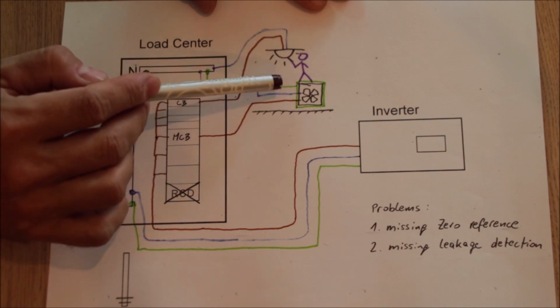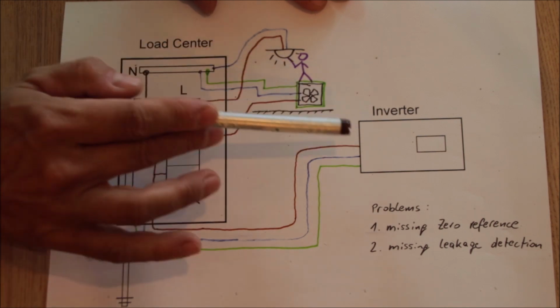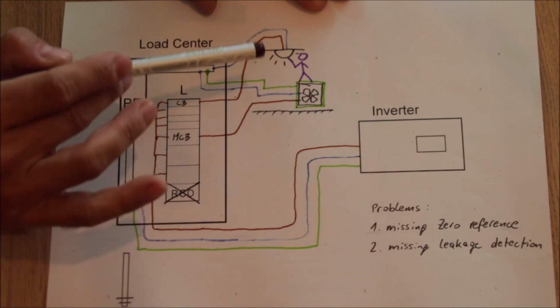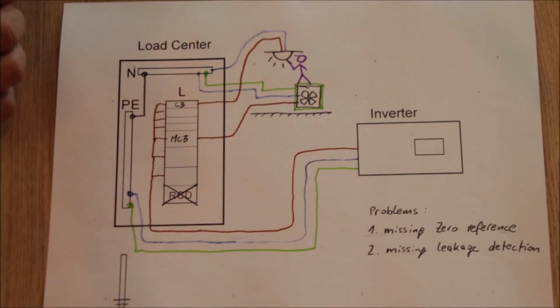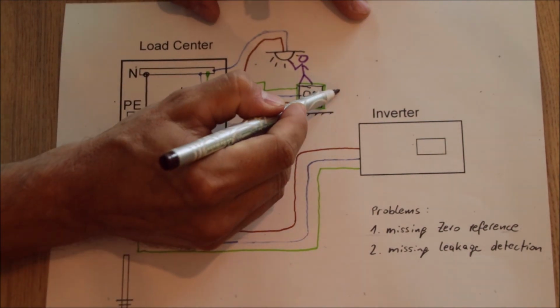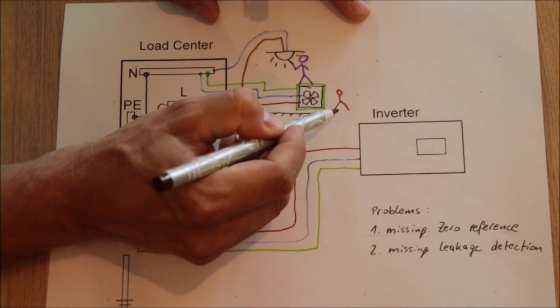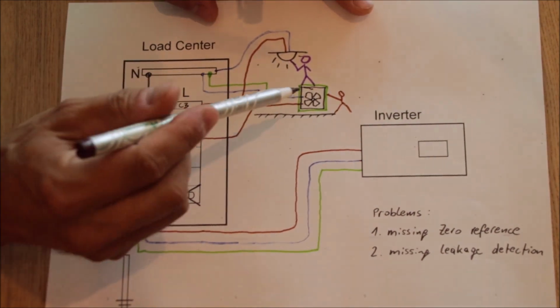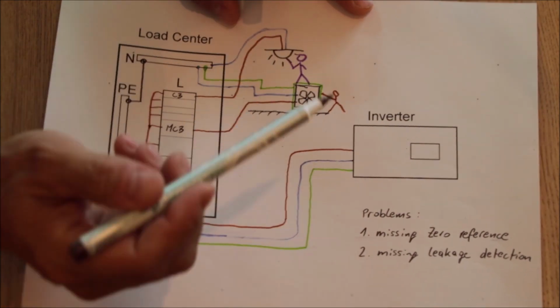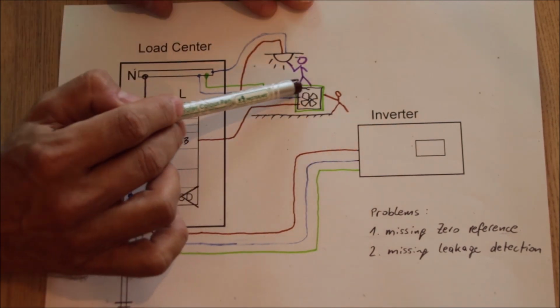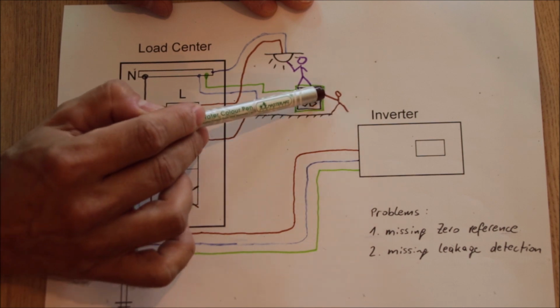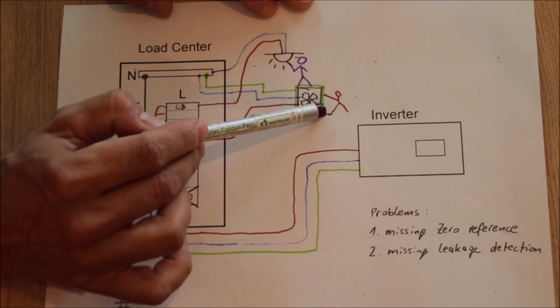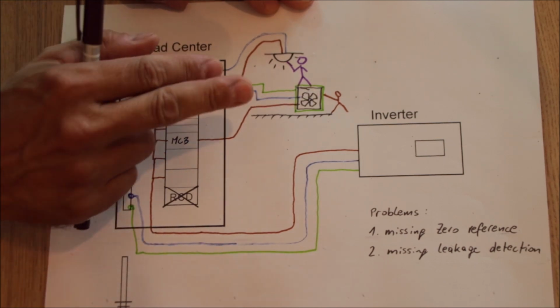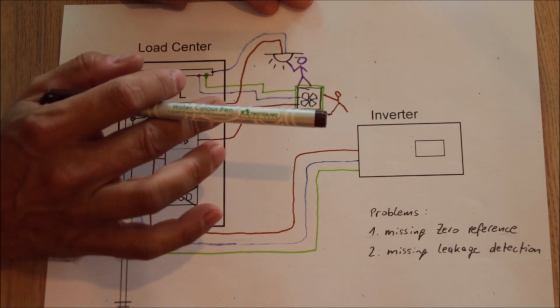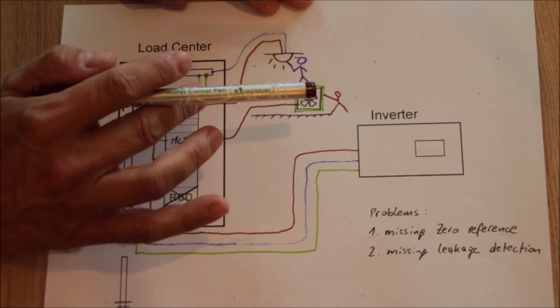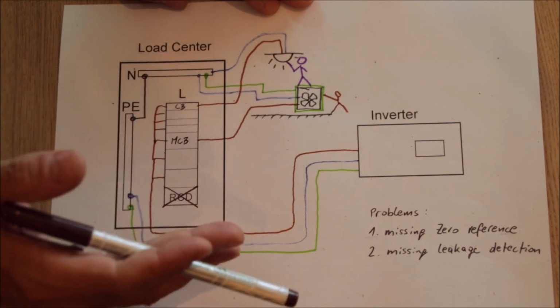To be voltage there is now not the problem, because we don't have any connection between power source and earth. So if a human comes here and stands on the earth and touches this, there will be no currents flowing over the human. So there is a potential here, but there is no closed circuit. So it is like static electricity there, right? If you touch the unit, maybe first time you could cause a spark, but it will be no continuous current flowing over you, which could kill you, right?